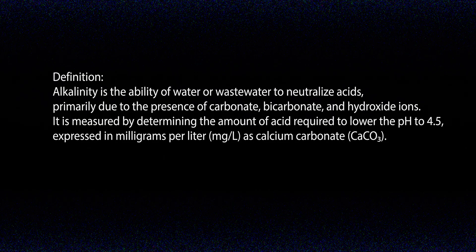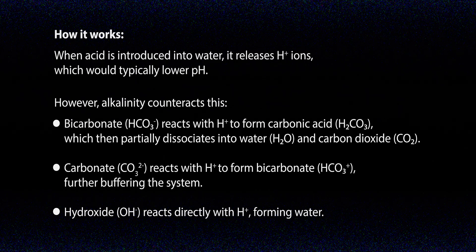Alkalinity is determined by performing a titration in a lab — essentially measuring how much acid is required to lower the pH to 4.5, the point at which all buffering capacity is used up. The result is expressed in milligrams per liter as calcium carbonate. When an acid is introduced into water, it releases hydrogen ions, which would normally cause the pH to drop. However, alkalinity acts as a buffer, preventing sudden changes. Bicarbonate reacts with hydrogen ions to form carbonic acid, which then partially breaks down into water and carbon dioxide, helping absorb the acid's impact.